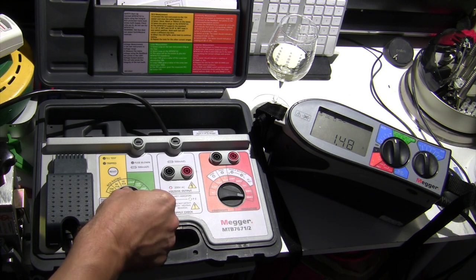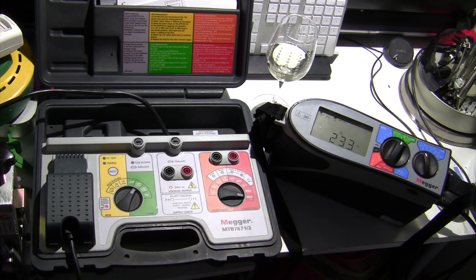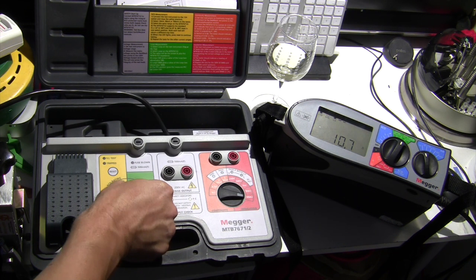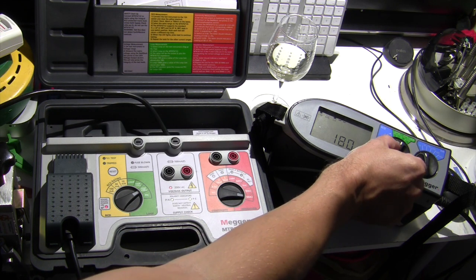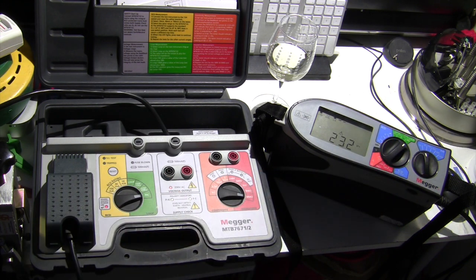I'm going to switch this now to loop plus 10 ohms. So from 1.43 we'd expect something around the 10.4 range, we're getting 10.7. And loop plus 180 ohms. Again, it should be consistent with what we're expecting to see. We're getting 180 ohms. And for the fault current test, I'm going to switch it to PFC. And on this circuit here, well, we're getting 21 amps.